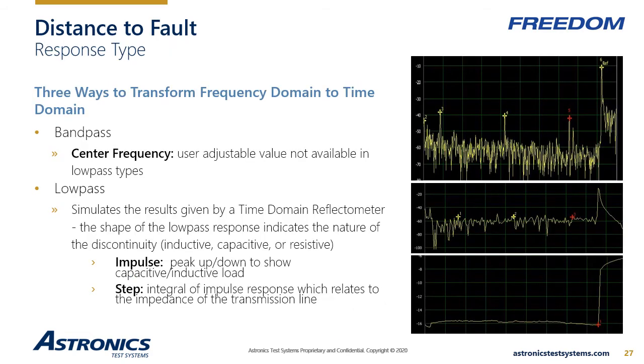The transformation algorithm that takes the frequency domain data and turns it into time domain data can be adjusted by the user to achieve different views. This parameter is called response type. When set to bandpass, the data is presented in true FDR mode. The user sets the center frequency to the center frequency of the operational band. The cable is swept and its performance in that band is presented as return loss.